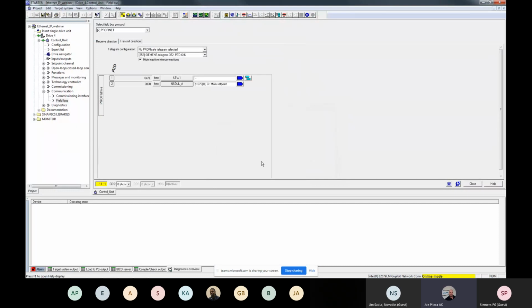So the first part that we are going to do here is a motor ID at standstill. So you will hear the drive cooling fan come on. The shaft might rotate a quarter turn or less. You will hear a series of high frequency rings from the motor while the motor data ID is in progress. And upon completing the motor ID, the drive will stop running and return to a ready state.